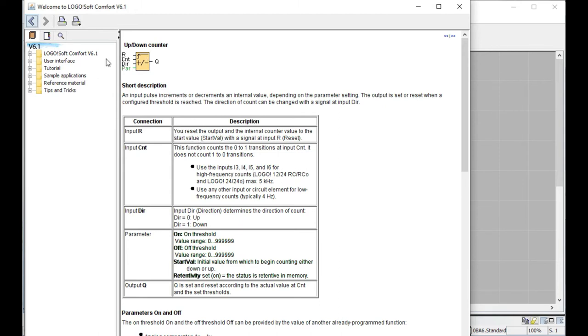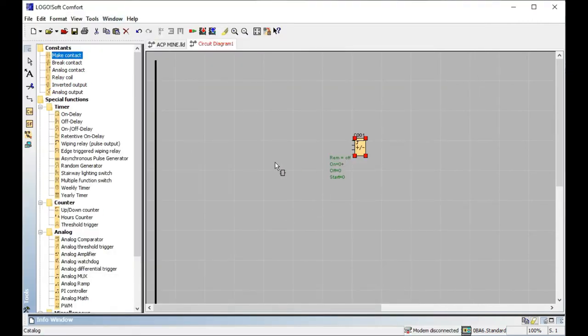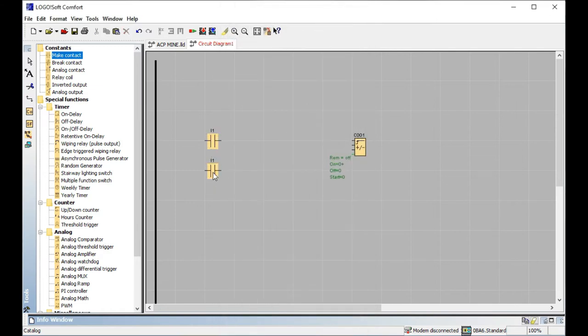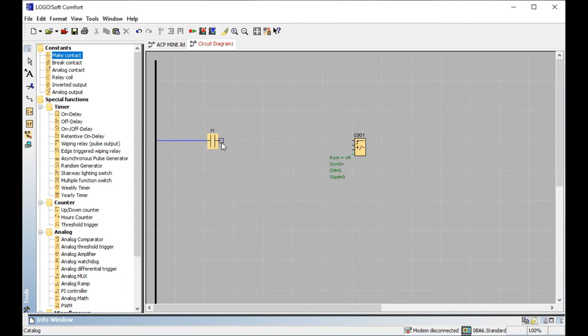Reset: when any sensor triggers, the counter will reset. The Count input (C) is where the counting pulse comes in — one, two, three, four, five, six — this is the counter value incrementing. The direction parameter: direction equals zero means up count, direction equals one means down count. Now let's go to the main part — I take a sensor as the input, connecting the sensing device to the counter's counting point.